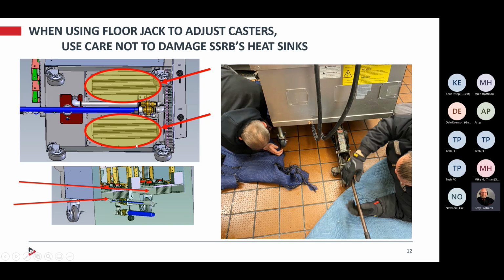The fins will bend, and or the solid state relay board will come crashing up inside the unit, causing a lot of damage. With that being said, right now you can see the 2 technicians here. They're adjusting my caster height. It's on the frame. Perfect. If the grill should slip and all of a sudden the jack hit the solid state relay board and it was plugged in, you could cause some arcing and could cause more failures besides just the one component. So always disconnect power before you're adjusting or repairing casters. Very important. You don't want that to slip and hit the solid state relay board.